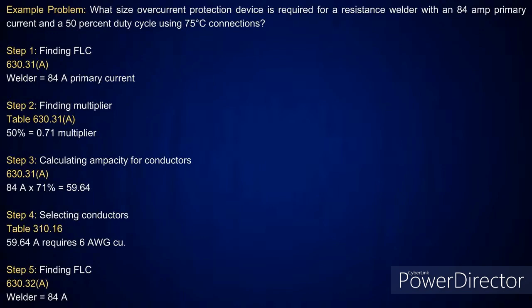Now, we're going to prove this to you one more time. We're going to show you a resistance welder here. In this one, you're going to look at 630.31A. When I'm doing non-motor and generator type, I'm in 630.11A. For resistance, you're going to look at 630.31A. Here I've got an 84 amp primary and a 50% duty cycle. So I automatically know my amperage from 630.31A. I'm going to use the nameplate, which is 84 amps. Now I'm going to look at this table down here and pick up the 50% duty cycle.